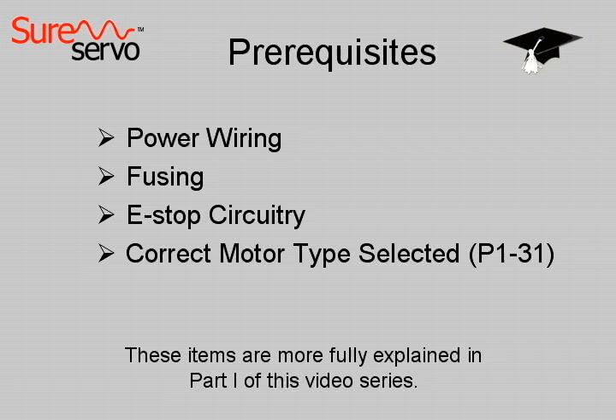We'll assume that you have already jogged the motor as shown in the earlier video. At this point, power, fusing, and an e-stop contactor should all be wired appropriately. See Chapter 3 for wiring information. The motor code in P131 should also be set to the correct motor type.